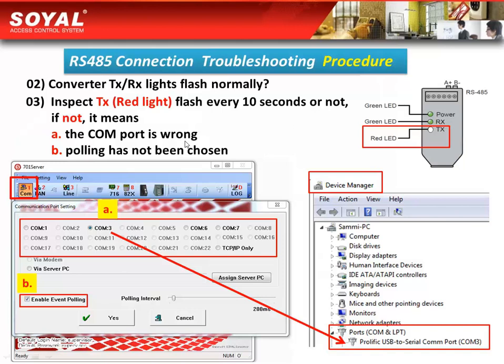Next, inspect whether the TX red light flashes every 10 seconds. If not, there are two possible reasons: first, the COM port is wrong — you can use Device Manager to confirm your COM ports. The second possible reason is that event polling has not been enabled. Remember, the event polling must be selected.